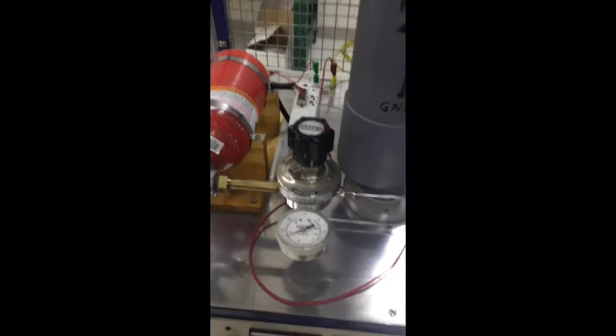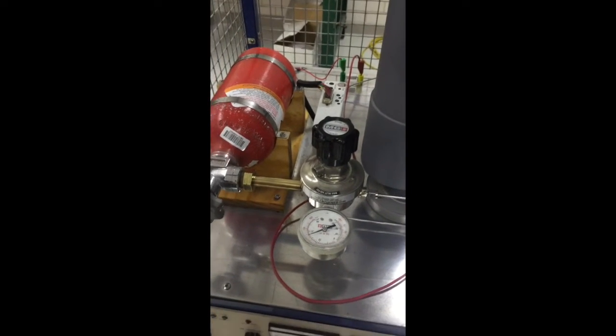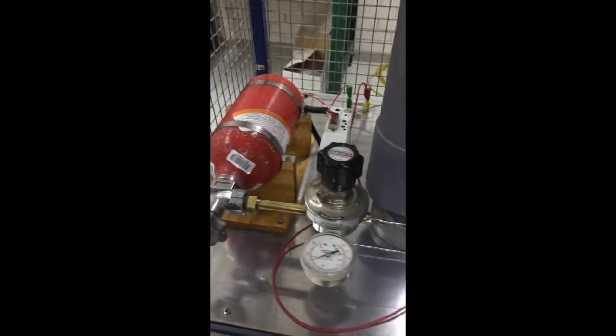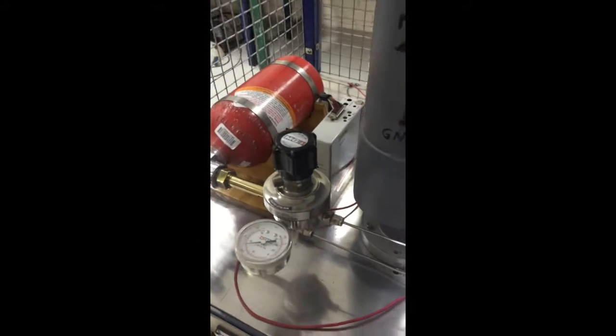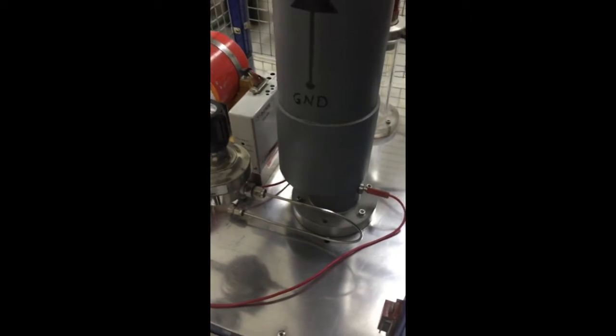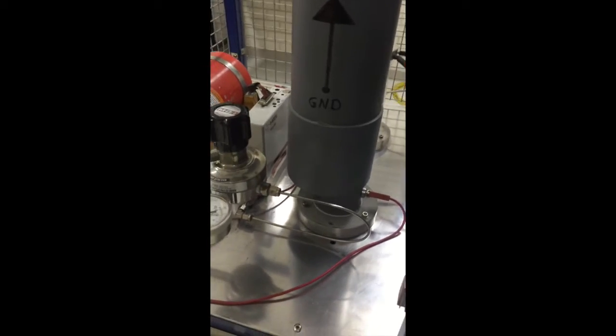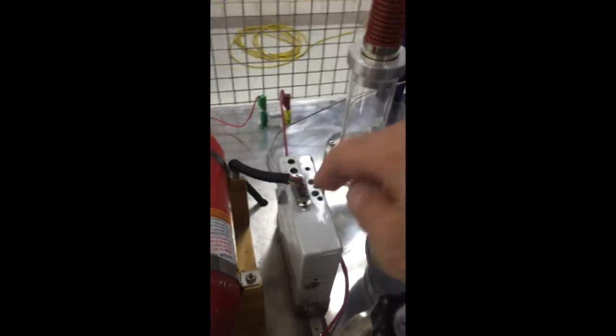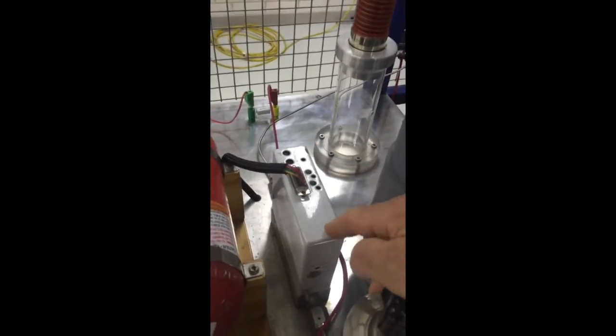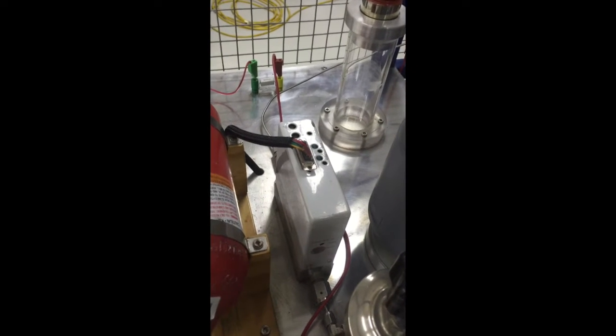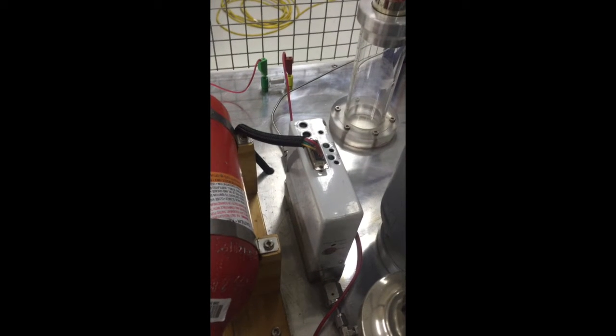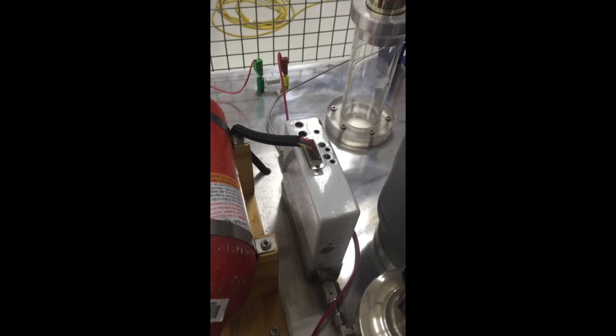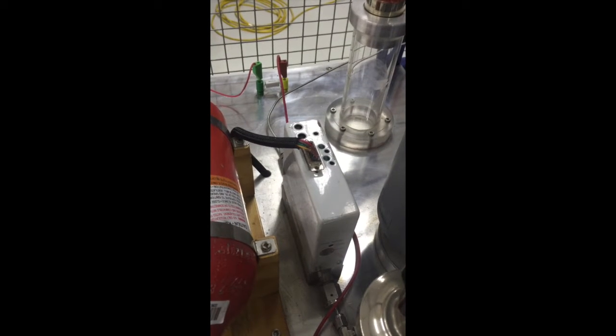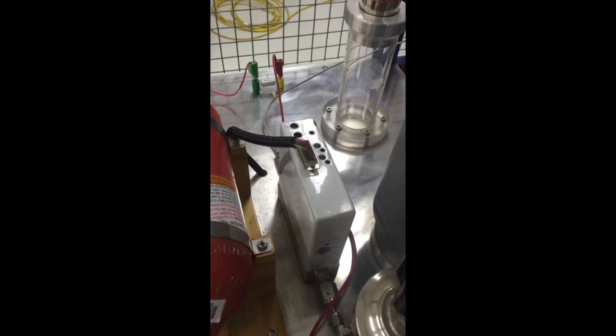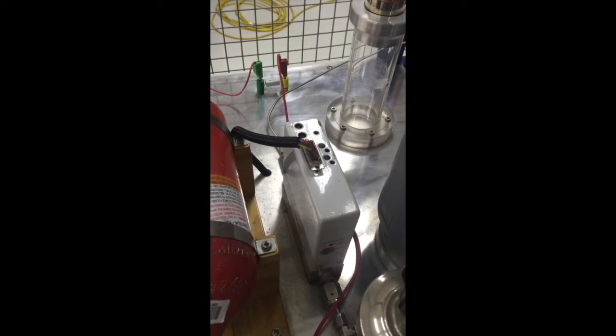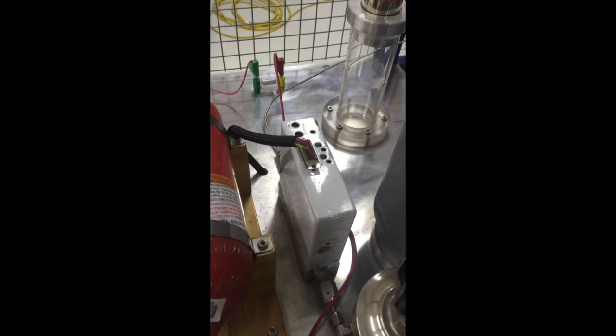I've got a single dial regulator on the deuterium, and this goes into Swagelok tube. I think it's 1/8 of an inch or something, and into this thing here, which is an MKS pressure controller. So it's not a mass flow controller, it's actually a pressure controller. From the remote LabVIEW, I can adjust the pressure and set it to 2 or 3 microns, and it'll just stay steady at that pressure.